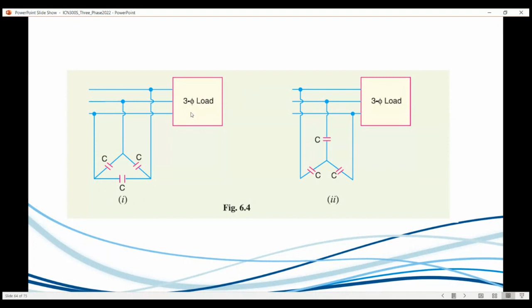Okay, so there is another way to correct power factor, and if we have time, we'll do synchronous motors, but I'll see. A synchronous motor can also be used for power factor correction, but if it is used, it's deemed a synchronous condenser. When we overexcite a synchronous motor, it produces a leading current, and then it will behave as a capacitor. So basically, this overexcited motor, when running on no load, acts as a capacitor. If it's connected in parallel with the supply, it essentially takes a leading current, which neutralizes the lagging part.